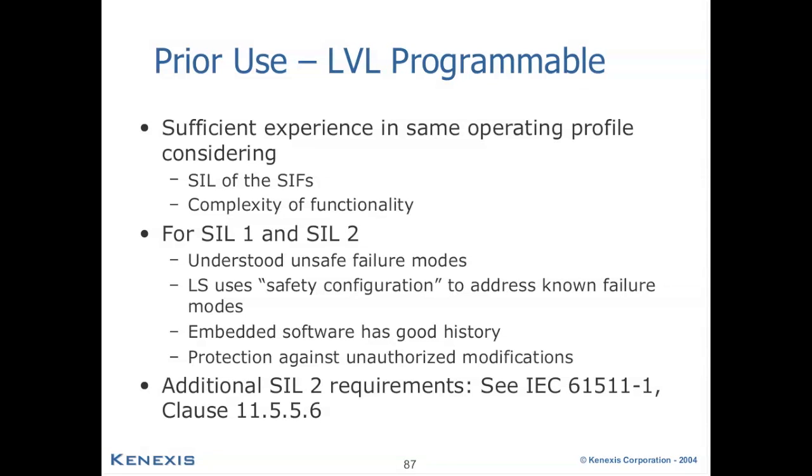For components with limited variability language, you'll want to demonstrate that the component has sufficient experience within the same operating profile, considering the SIL of the SIF and the complexity of the functionality. For SIL 1 and SIL 2 particularly, you'll be concerned with the device having understood unsafe failure modes, and since most of these components involve logic solvers, having a safety configuration to address known failure modes.